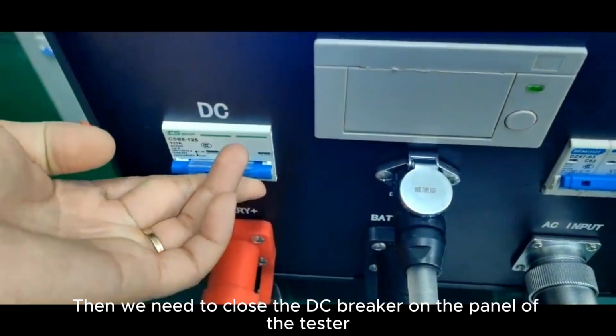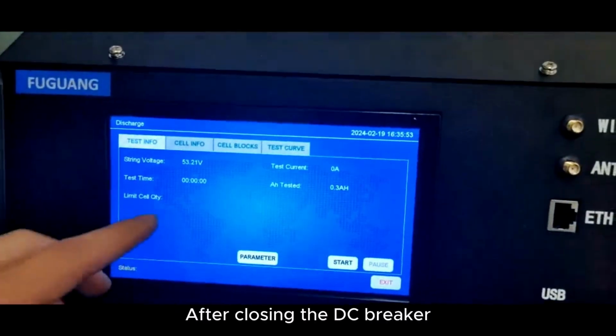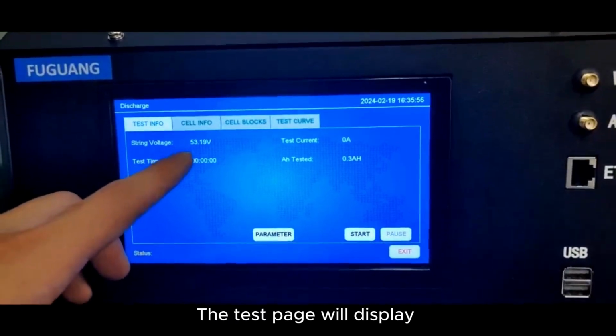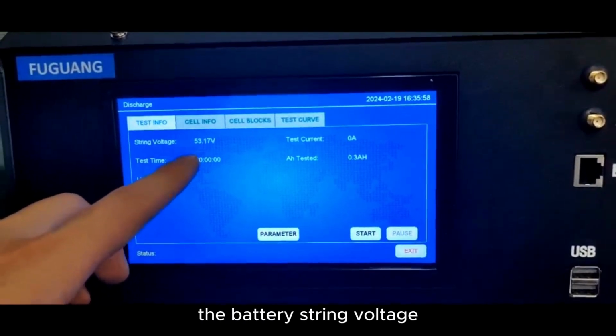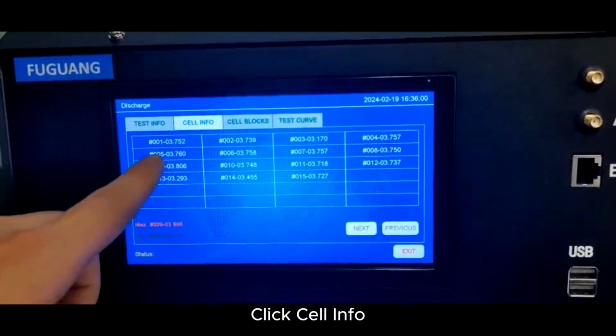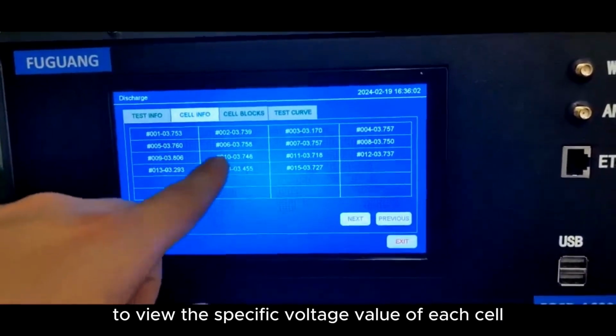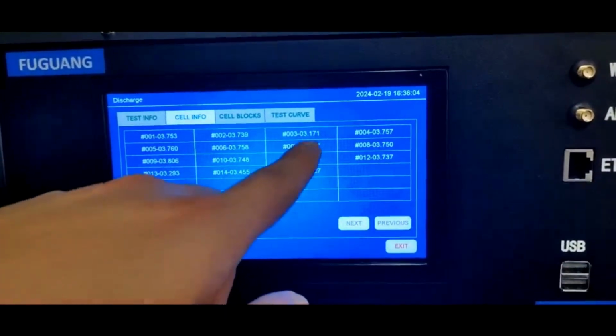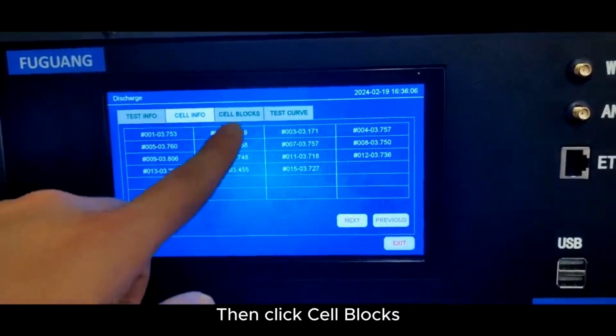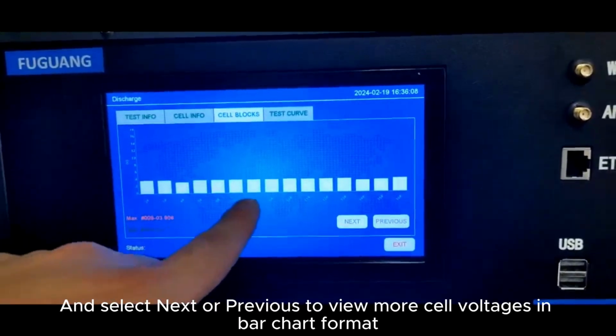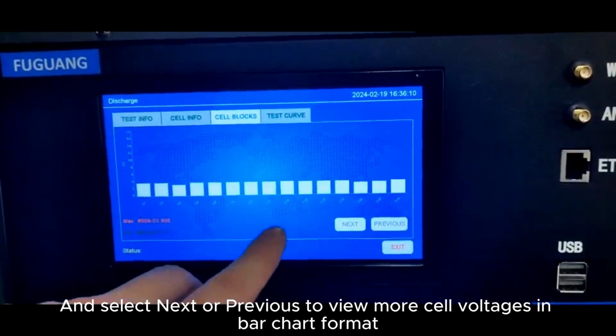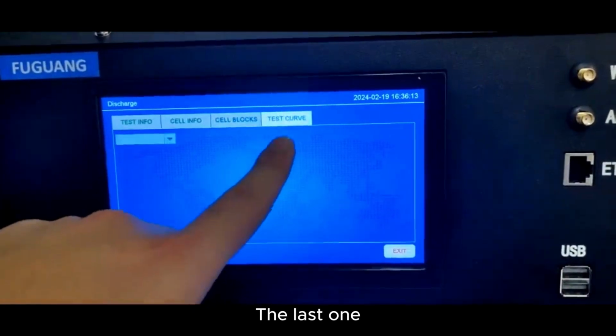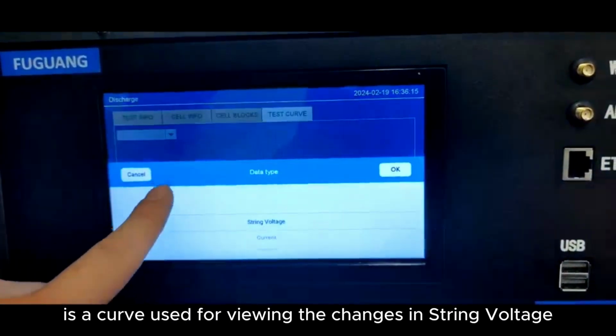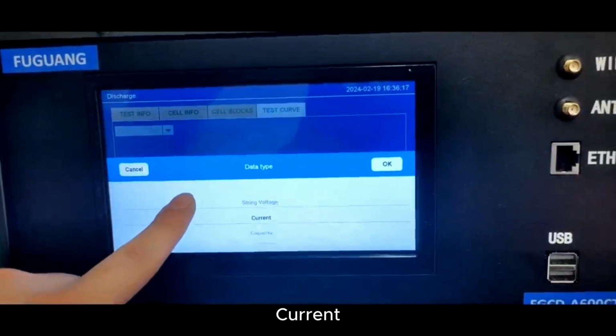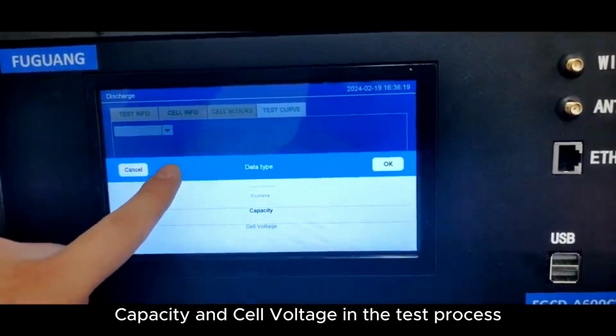Then we need to close the DC breaker on the panel of the tester. After closing the DC breaker, the test page will display the battery string voltage. Click Cell Info to view the specific voltage value of each cell. Then click Cell Blocks and select Next or Previous to view more cell voltages in bar chart format. The last one is a curve used for viewing the changes in string voltage, current, capacity, and cell voltage in the test process.